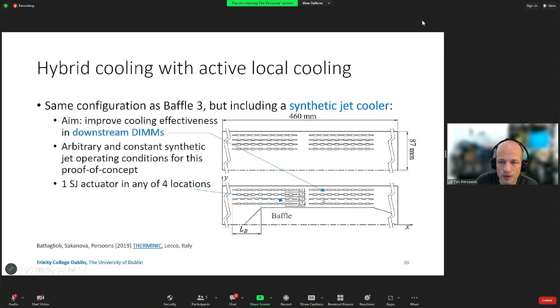So what we propose here is to introduce one single synthetic jet cooler in any of these four locations. We won't have four, but just a single one, either between these DIMM modules or here or here or here. And we look at a simple optimization, similar to what we had before with the baffle in the middle, so that we can channel most of the flow to go through the DIMM modules, and we get this additional cooling effect of a synthetic jet cooler.